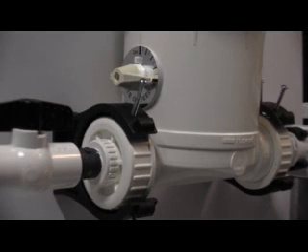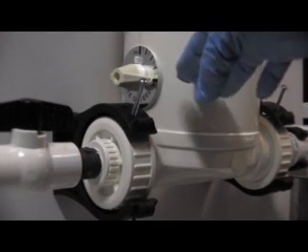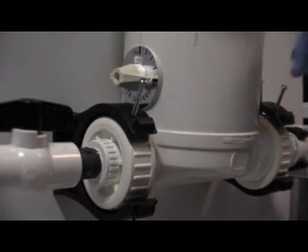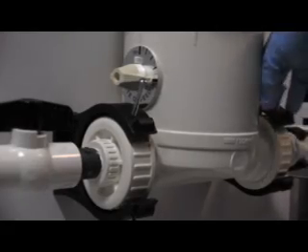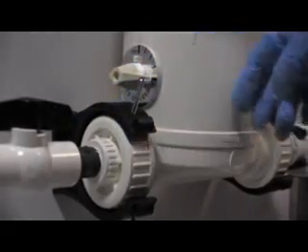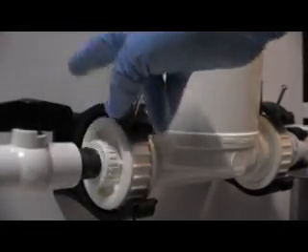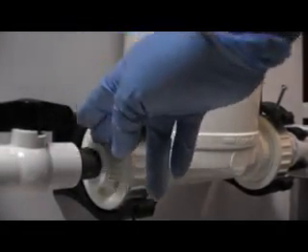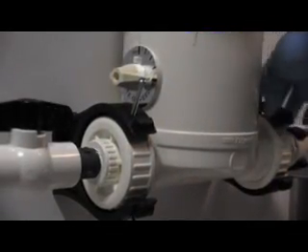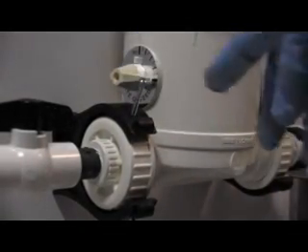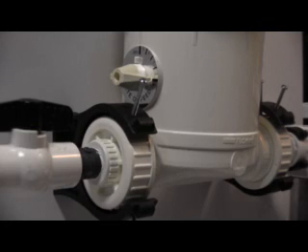Okay, are you starting to get the idea of differential pressures? So folks, if you're going to go to a spray cabinet with this unit, I would recommend that you put in a pressure gauge on the inlet side and a pressure gauge on the outlet side, and make sure that you have that pressure differential. Because if you don't, it's not going to work ideally. Okay, I'm not going to say it's not going to work at all, but it won't work ideally.